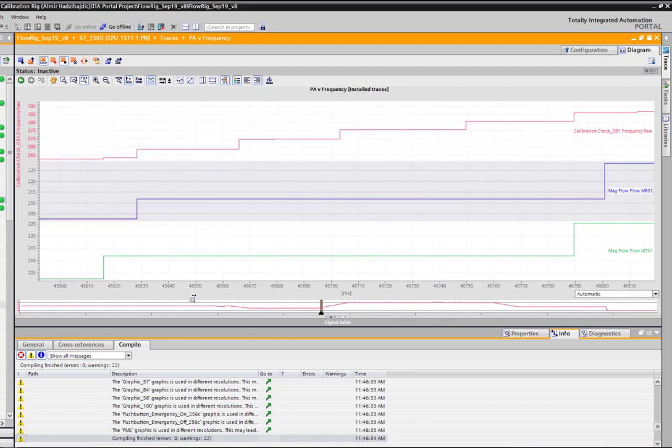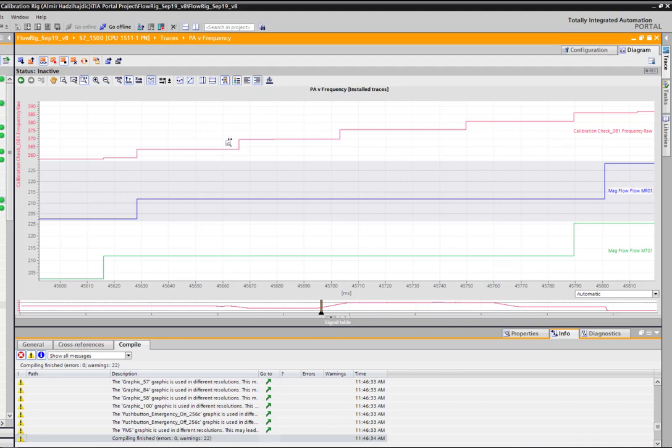If we have a look at the results here this is in milliseconds so we are looking at a response time of about a hundred milliseconds which is 10 hertz which is relatively fast. But in that time the high speed counter has taken one, two, three, four and a half measurements in one PROFIBUS PA update.